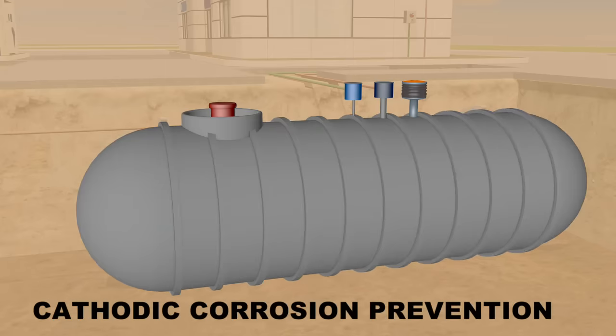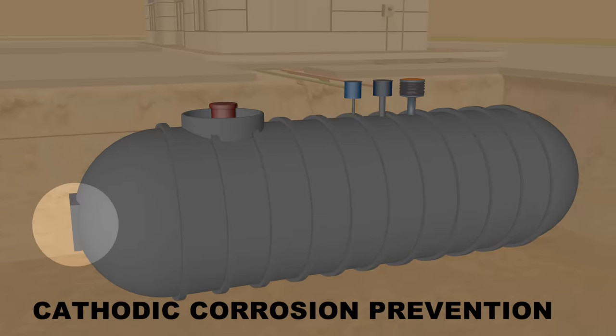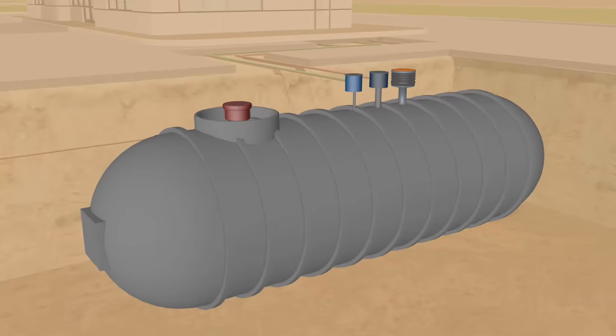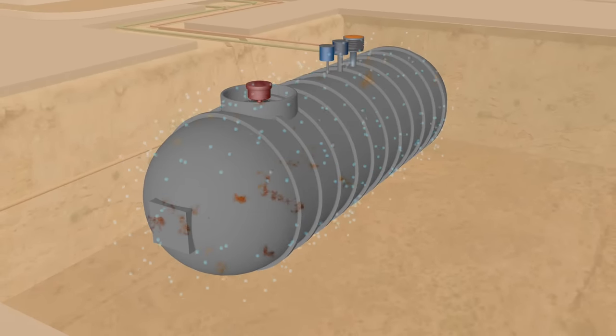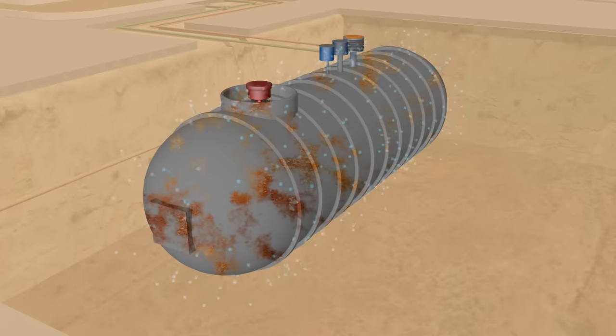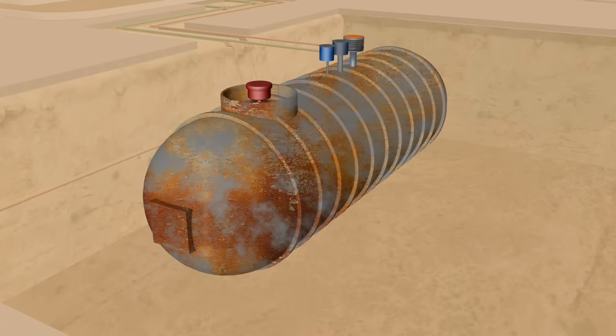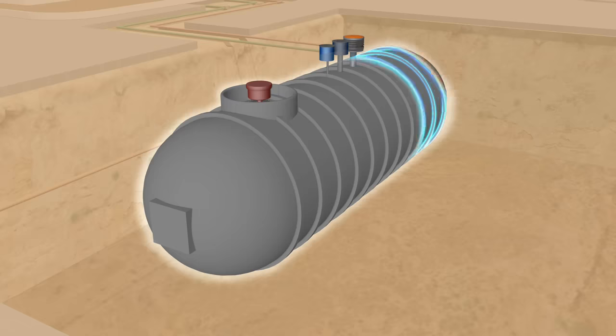When uncoated steel tanks are used, cathodic corrosion prevention systems are required. Corrosion, or rust, is caused when moisture in the soil draws off electrons from iron molecules in the steel. Applying a slight electrical current, basically a stream of free electrons, helps keep the iron molecules intact.